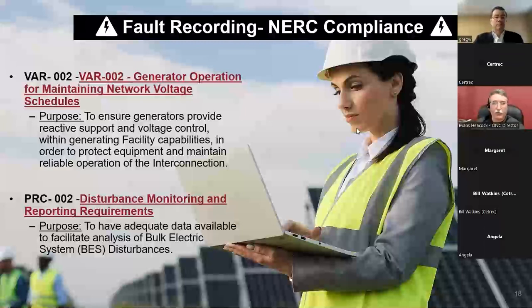There are sites required to meet the PRC2 disturbance monitoring recording requirements by NERC. These would actually install very easily for that purpose, from the sequence of events type item or fault recording, and also what they call dynamic disturbance monitoring.